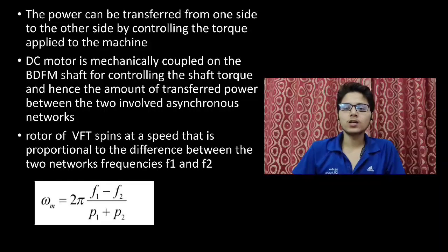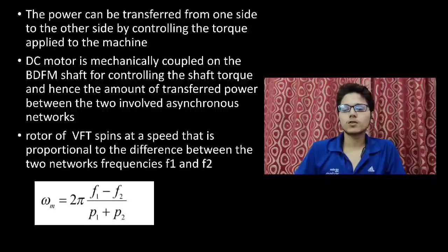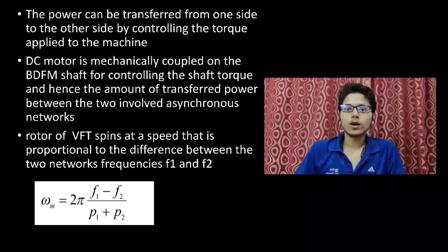The proposed BVFT is similar to the conventional VFT using DFIM, where the BVFT is used to connect two networks experiencing a slight difference between their frequencies. The two networks are connected to the two stator windings. The power can be transferred from one side to the other by controlling the torque applied to the machine.